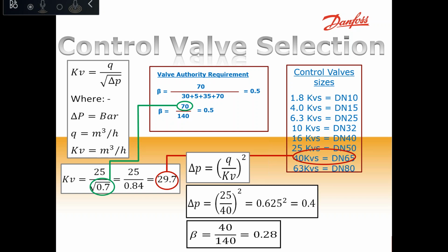So if we have an equal percentage valve and we have an authority of 0.5, we are having at least 70% of the flow that can be controlled. But in real life, what is happening on site, there will never be 50% authority on a two-way valve for the simple reason that if you are close to the pump, we have a very high pressure drop available from the system. Because people, when they calculate the two-way valve authority, they consider only the coil and the pipe and strainer around the valve, but they don't consider the available pressure coming from the system. And if you are near the pump, you have 4 bars available, so your authority will be 0.1. So for that reason, a two-way valve will never be able to achieve a good authority.